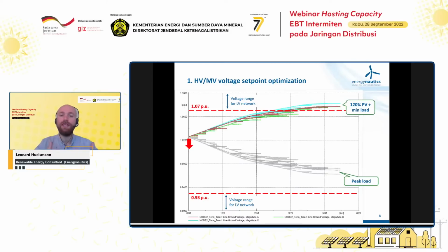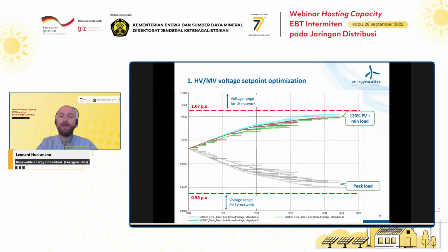What you could do as a mitigation measure is operate the distribution network in a different way, by decreasing the voltage set point at the start of the distribution feeder. This would be at the primary substation transformer. If we lower this in this specific network, the starting voltage would be decreased, and so during this time of PV generation, we would have the problem resolved. It's no longer hitting or going above the red line here. Still we have no issue with regard to peak load. Also during times of peak load, we don't have any under voltage issues either.